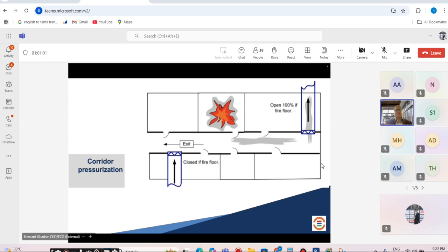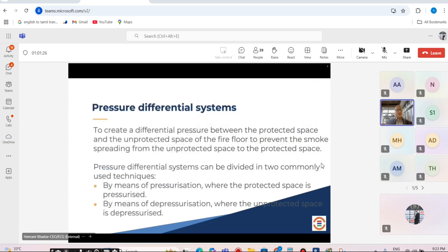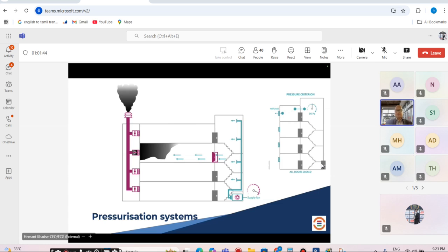So you have to really see whether a differential pressurization technique or system has been used, so that you will not have imbalanced pressurization or a force on the door which is higher than what is expected for a human person to use it. So pressure differential systems are more popular, where you will be able to mitigate the risk and see that it is protected uniformly. That's how the systems are now well engineered when coordinated with other building engineers.